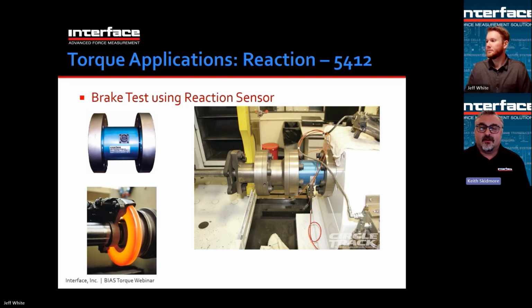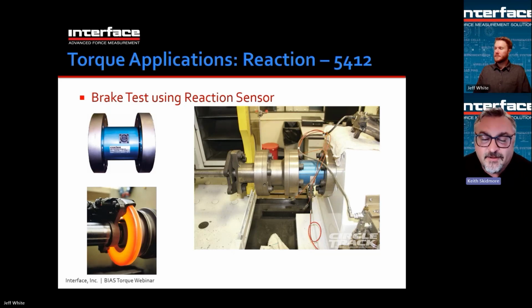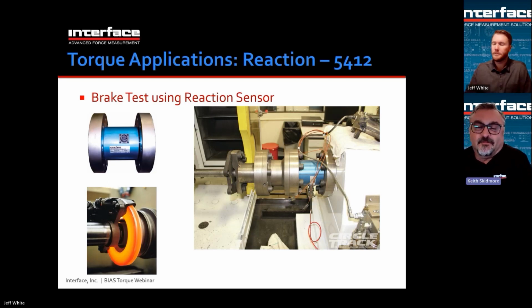Here's an example of a brake test. This is our model 5412, 50,000 inch-pound torque sensors, which is about 5,000 Newton meters. You can see that the rotor being tested is running red hot. The spinning assembly is attached to the brake disc that spins, and then the caliper is actually attached to the part that's attached to the torque sensor. So it's a reaction torque sensor being used to measure torque generated from a rotating brake. Commonly done. Moving on.